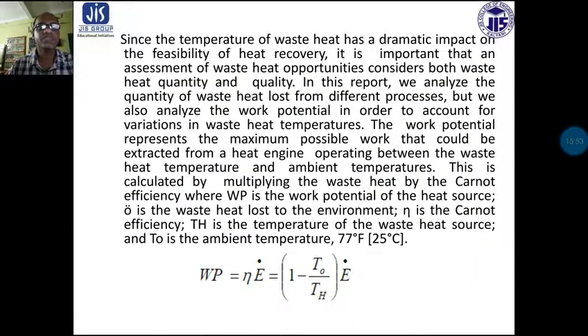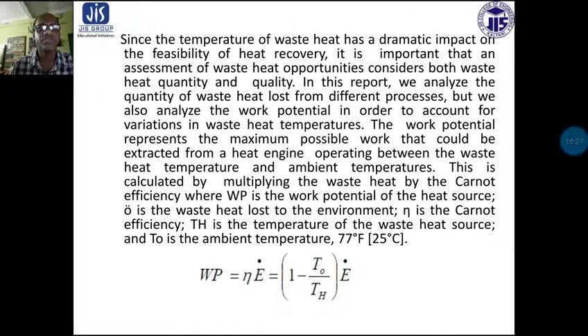Since the temperature of waste heat has a dramatic impact on the feasibility of heat recovery, assessment of waste heat opportunity must consider both quality and quantity. We analyze the quantity of waste heat lost and the work potential, which represents the maximum possible work extractable from a heat engine operating between the waste heat temperature and ambient temperature. This is calculated by multiplying the waste heat by the Carnot efficiency, where Wp is the work potential of the heat source.